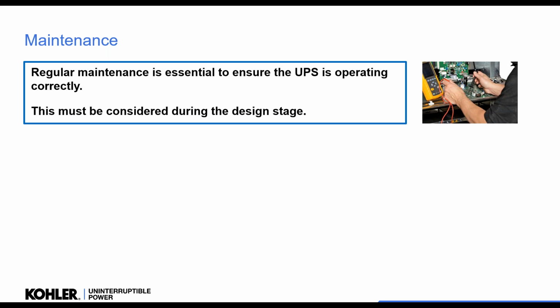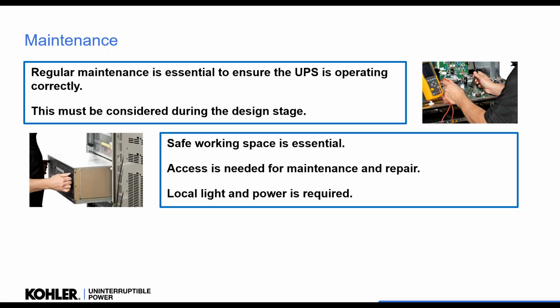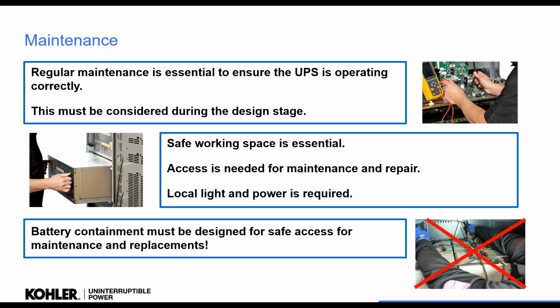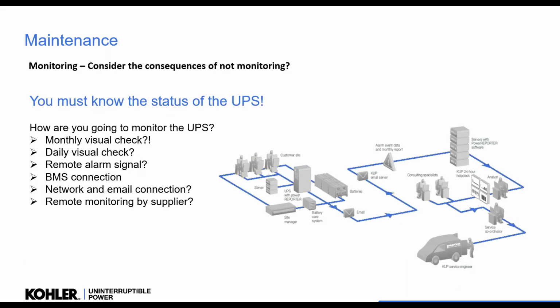This is not always done, especially unfortunately on life safety systems. We must consider, so put it in a place where we've got safe working space, we've got local light and power, and we can get in there and maintain it safely. Some of these battery systems are quite high voltage. We're talking sort of 600-700 volts of DC, and we don't want to be leaning over an unsafe battery trying to maintain it and replace it. Okay, so it's very important that we do that, from day one, that we maintain it in a safe way, okay, and design it to be safe. Okay. So it's important that we do all these things.